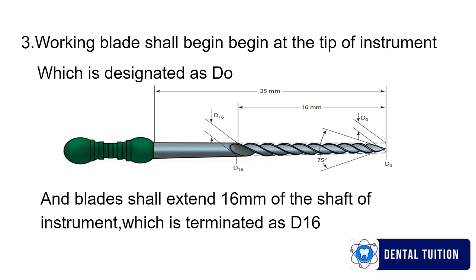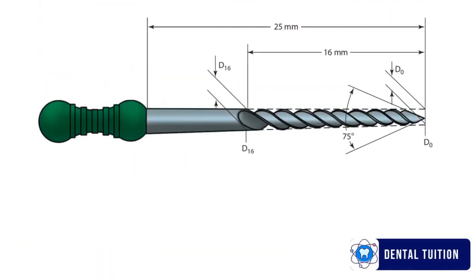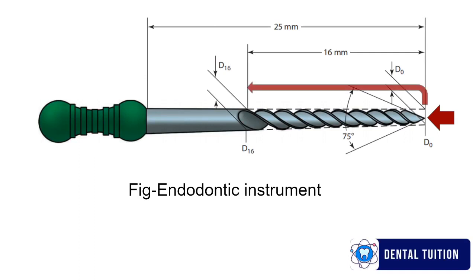Now proceeding towards next recommendation, the taper of the instrument shall be present, which should extend from the tip of the instrument which is D0 to D16. D16 is the diameter where the blade ends.